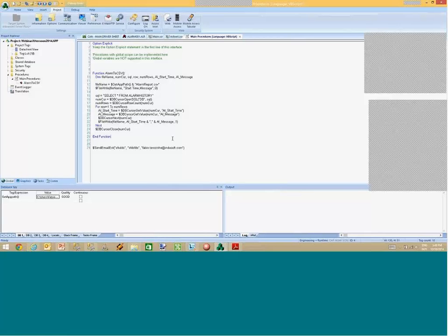So pretty much you can create a script where every time you have a new alarm, you insert a record. Typically that's the way we do it. Whenever a new alarm becomes active, if it is an alarm you want to send by mail, we insert a record in a table, in a database, and then according to your escalation criteria, check the messages in this database while they are still active and resend them to new users if they have not been cleared, if they have not been acknowledged yet.